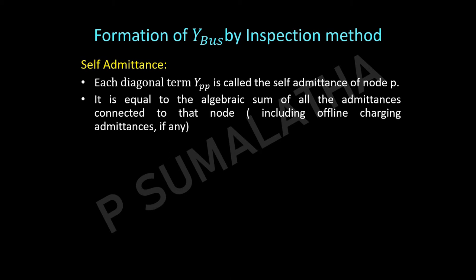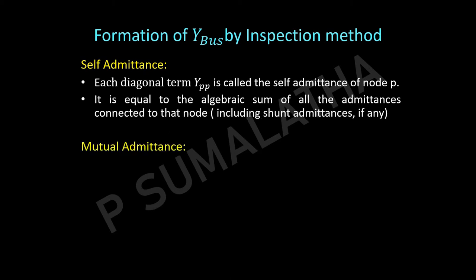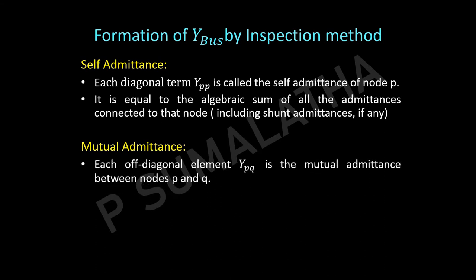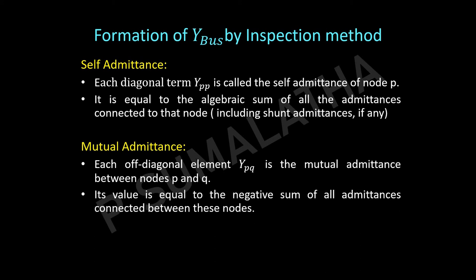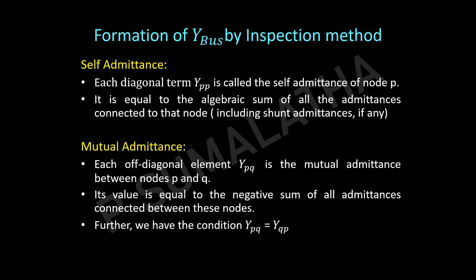Line charging admittances or shunt admittances also need to be considered in the calculations. For the mutual admittance, each off-diagonal element Y_PQ represents the mutual admittance between nodes P and Q. That value equals the negative of the admittances connected between those two nodes. If two transmission lines are connected between two nodes, we add those two admittances with a negative sign. Also, Y_PQ equals Y_QP.